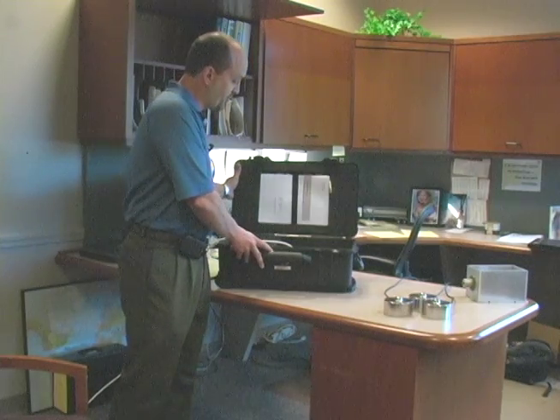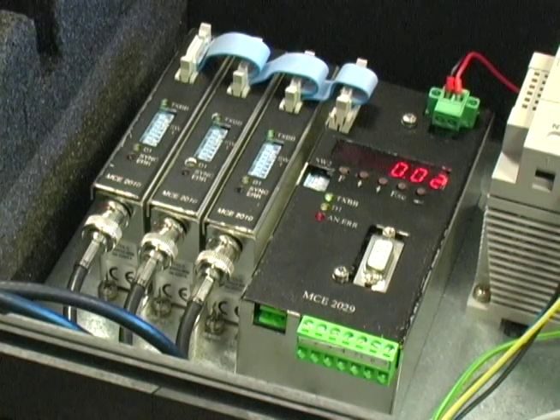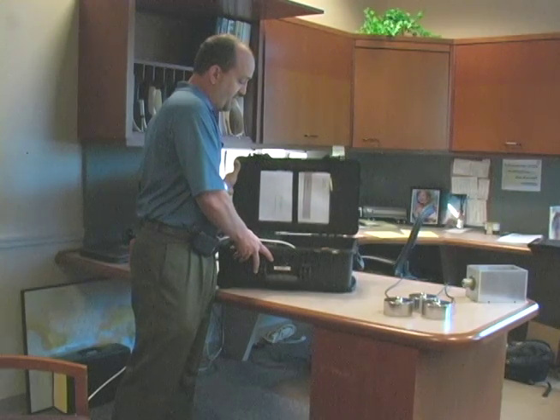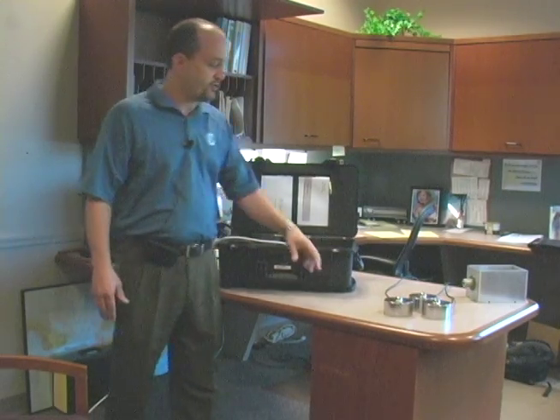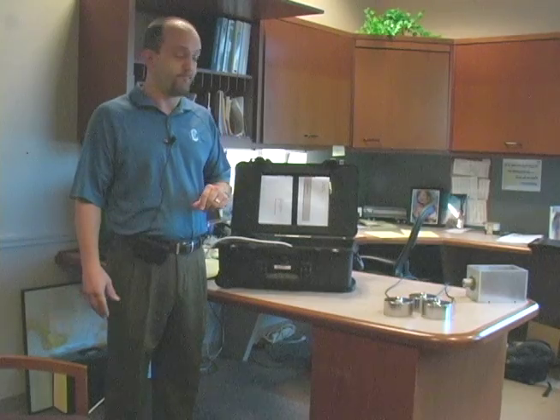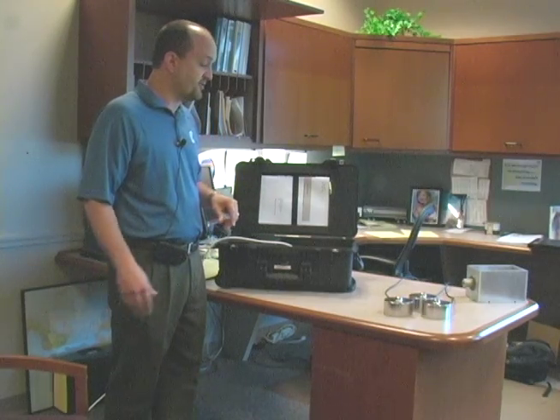The next you'll have what you can see in the case as your scale and your processor head. The scale element is matched to the individual load elements, and each scale element goes to one processor head. The processor head basically sums all the scale elements as well as sends out the digital signal to your PLC or display as it may be.